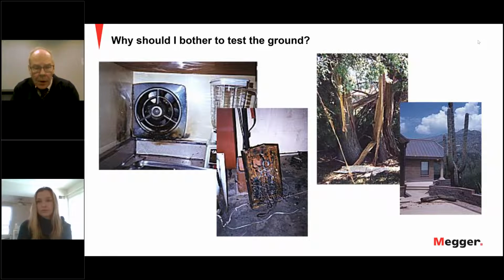And so the problem with grounding electrodes is they corrode away by the natural effects of the soil around them. One of the grounding materials companies a few years ago, and this was Lyncole XIT, you can probably find this up on their website, actually did a study of installed grounds, and they determined that in as little as 2 years, they started to see substantial corrosion in the worst of environments.